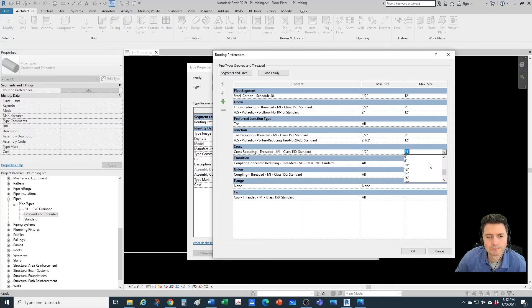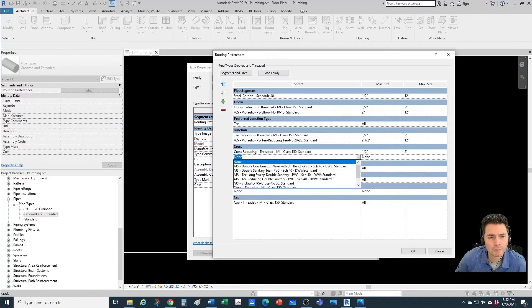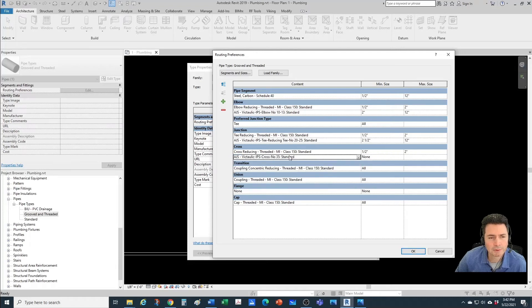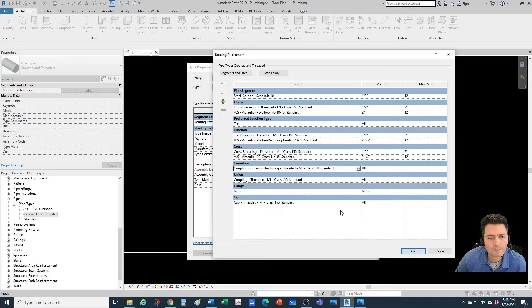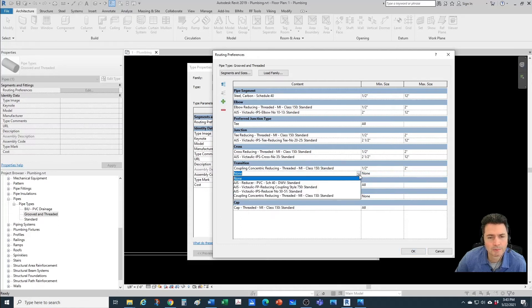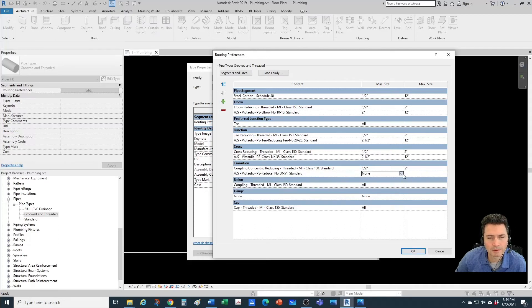The grooved cross is Victaulic number 35 from two-and-a-half inches up to 12 inches. You'll notice I have 'AJS' at the front of my fitting names — that's just for me to identify them faster. For transition: same thing, half inch to two inches gets the threaded coupling concentric reducing, then we add the grooved section which is the 50/51 in this case, from two-and-a-half to 12 inches.